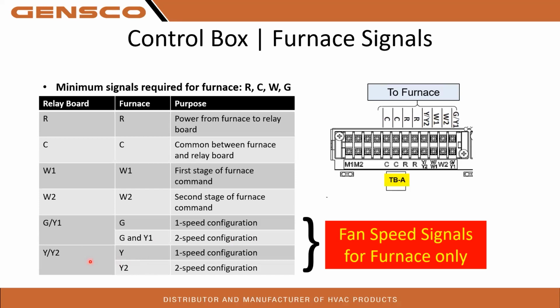We don't want that. So if you're running a one-stage furnace, you're going to connect G to the G terminal and Y to the Y terminal. That way you have your fan control and your call for fan and cooling, essentially. If you have a two-stage furnace, you're going to jumper G and Y1 together and wire them together right here. And your Y2 is going to wire up to the Y2. And again, we have more wire diagrams in this a little bit later in the slides. We'll get a little bit more into it.